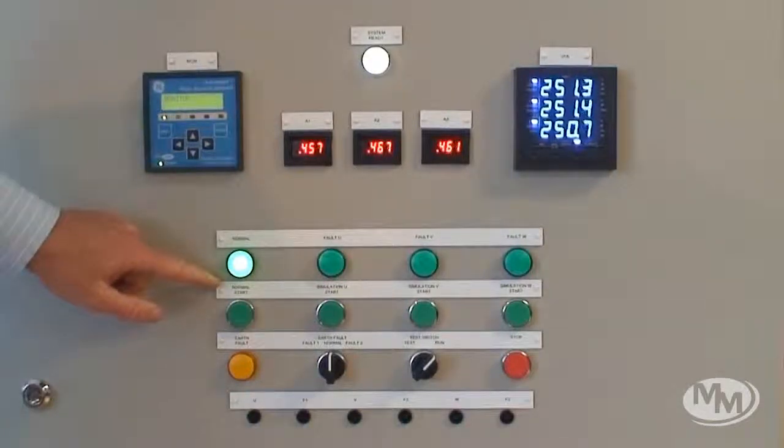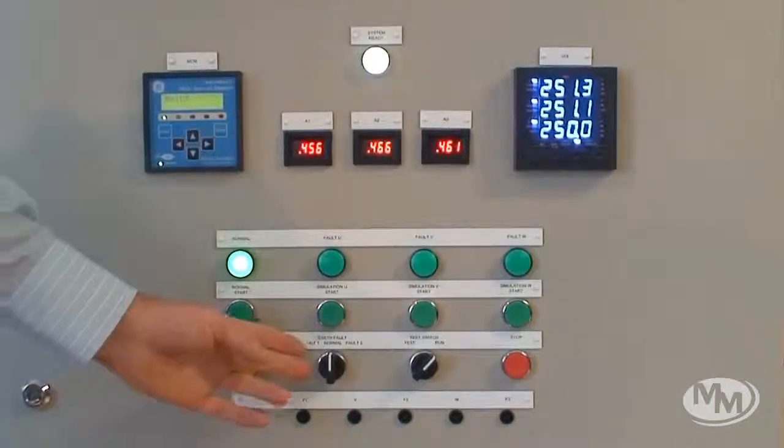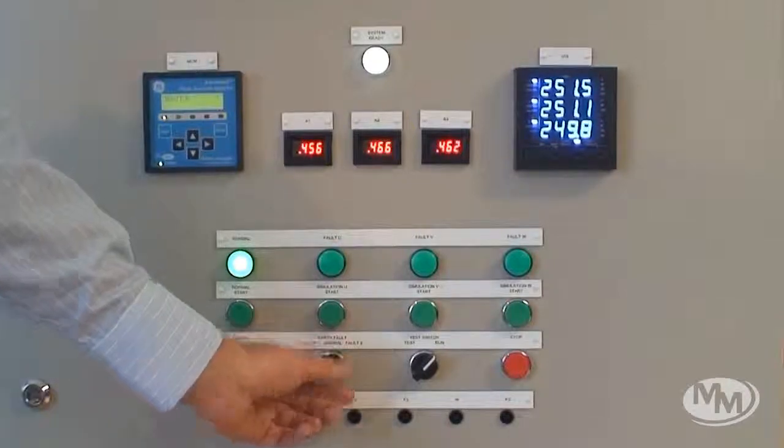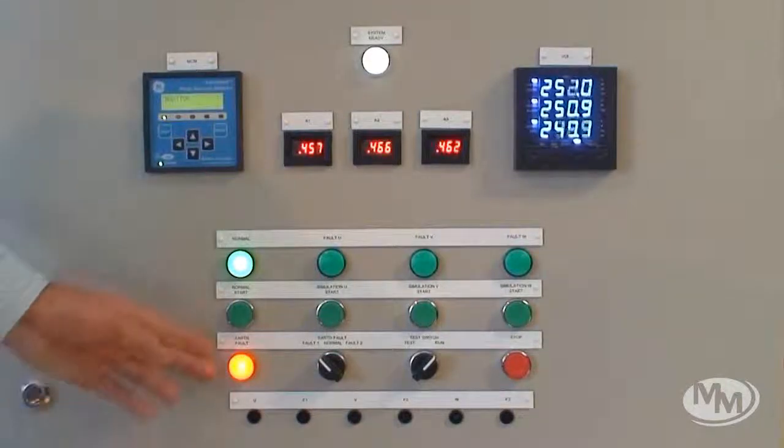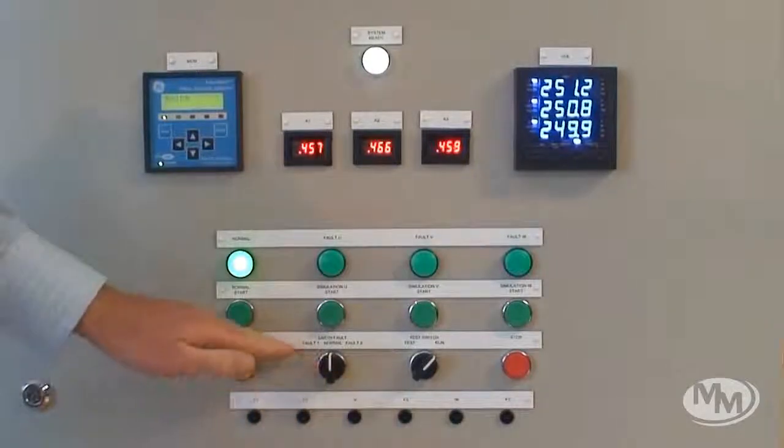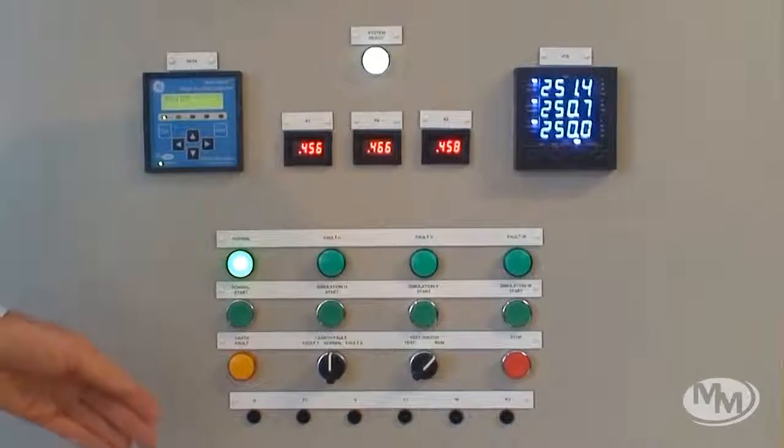We can also introduce earth faults. At the flick of a switch, an earth fault is introduced on the test motor's stator winding. There are two levels of earth fault, fault 1 and fault 2. These simulate a higher impedance fault and a lower impedance fault.